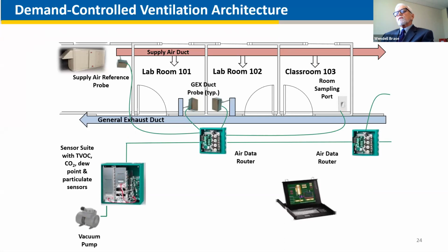It doesn't do it this fast in real time. It does it about every couple minutes because for each one of those air packets that's coming down to the sensor suite, it's evaluating all those things: total VOCs, carbon dioxide, carbon monoxide, dew point, particulates down to a pretty low, or a very high, level of resolution. All that data is ending up at a web-based user interface, which I just mentioned.